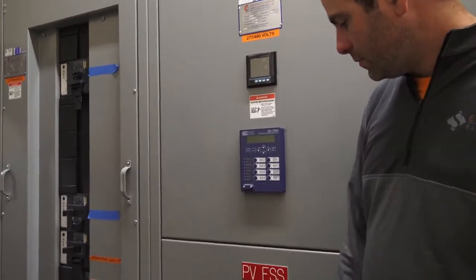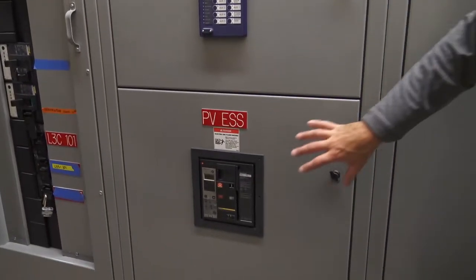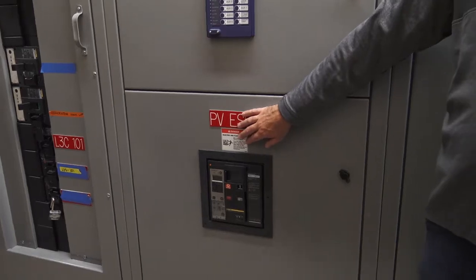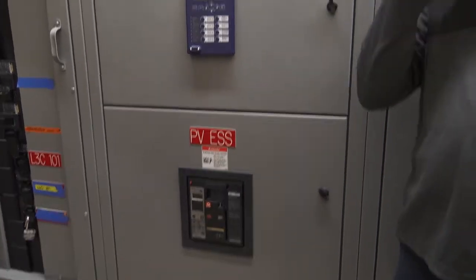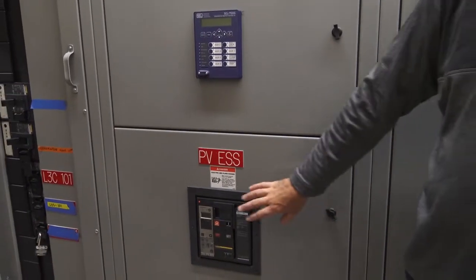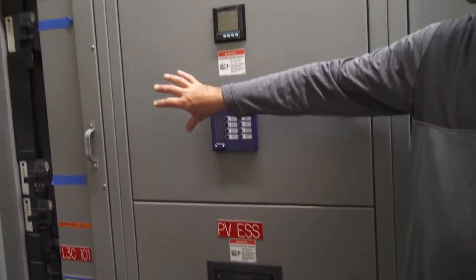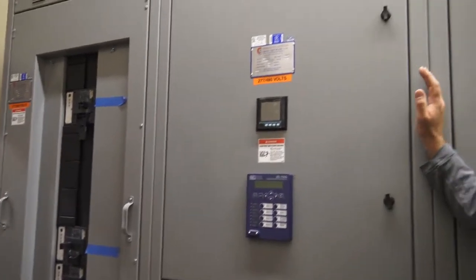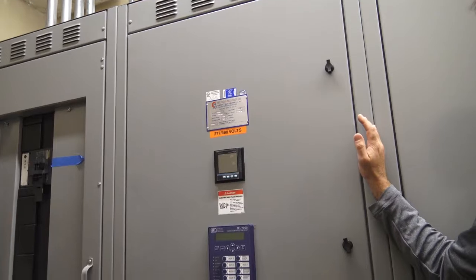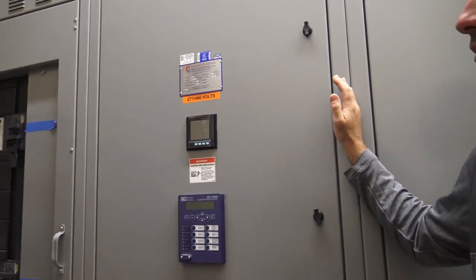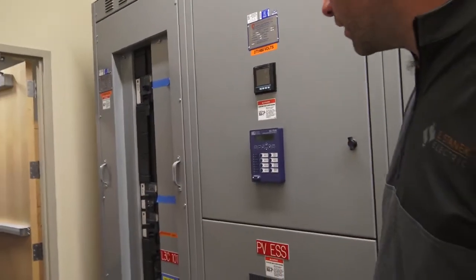So this breaker is getting fed directly from that 800 amp breaker in that room. It comes over here and feeds this, which feeds this whole section. So all of this is considered emergency - our life safety, our critical, and our equipment branches are all fed out of here.